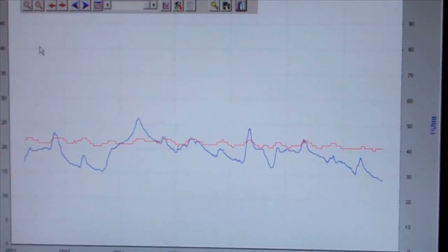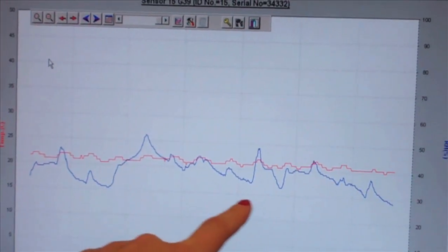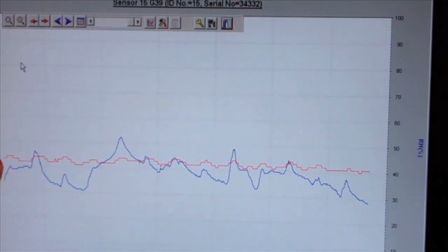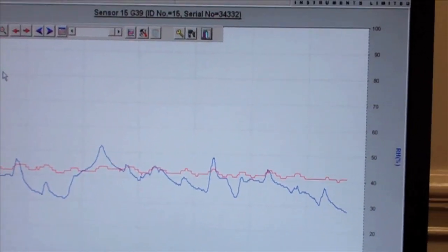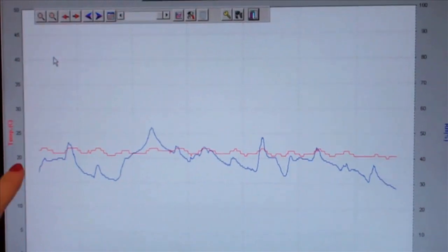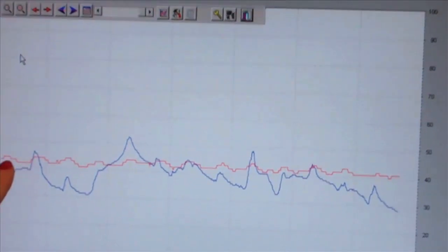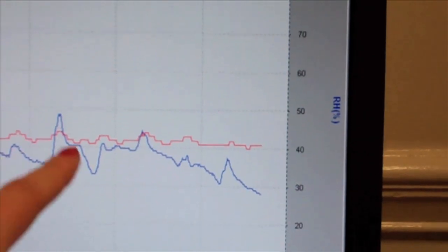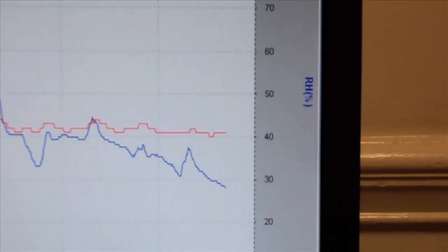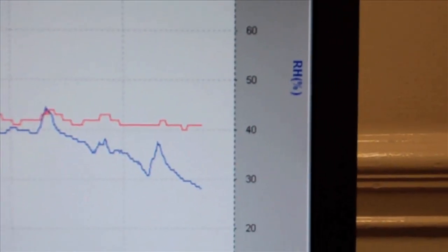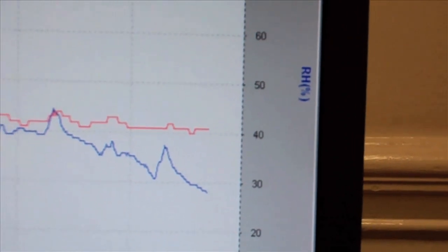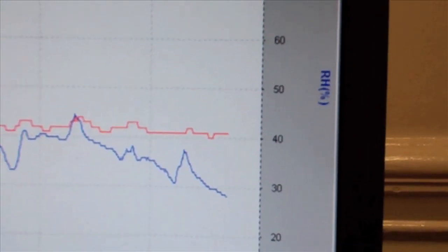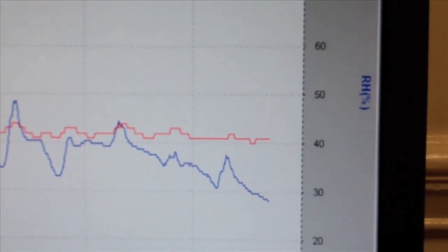Yeah, basically what you can see on this chart is the blue line which is relative humidity and the red line which is temperature. As you can see this has got quite a lot of fluctuation here and relative humidity is most of the time below the range we would like it to be, which would be between 40 and 65%.